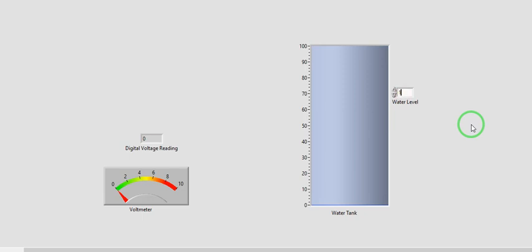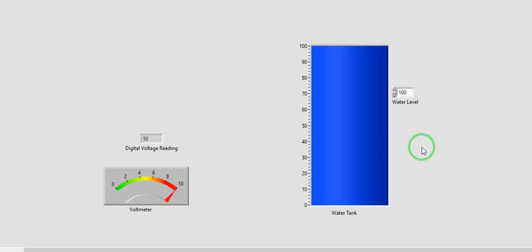At 100 feet, 10 volts. So if you have between 0 and 100 feet of water level, then you will have output voltage of the level transmitter between 0 and 10 volts also. So for example, you have 78.5 feet. Output voltage is 7.8 volts.